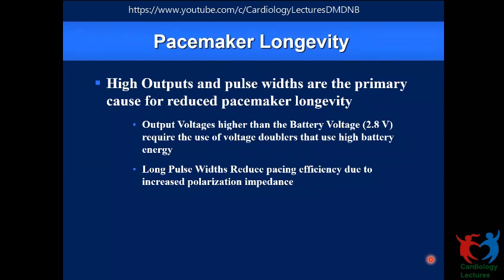What is more relevant is to make sure the safety margin is not compromised. That's why you program the output at twice the threshold. And pulse width, we generally do not compromise, do not interfere much or vary much, unless the thresholds are very, very high. Only then would adjusting the pulse width make a difference, because otherwise you'll drain the battery early. Okay, okay, sir.